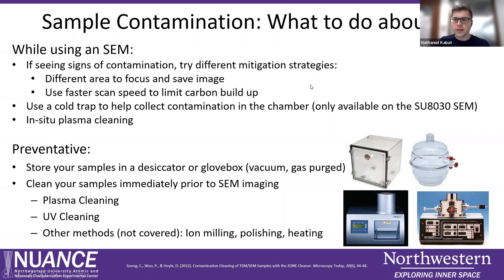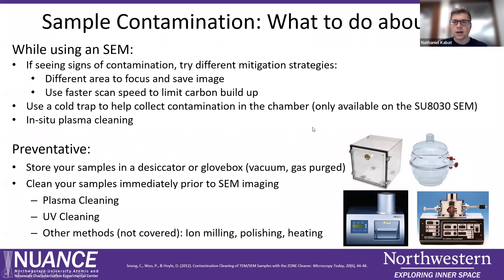Let's talk about a few different things you can do to mitigate, minimize, or attempt to fix contamination altogether. While you are actively using an SEM, you can do your focusing and alignments at a high resolution in a different area from where you save an image, to minimize buildup in the areas where you collect an image. In some cases you can simply use a faster scan speed to help limit carbon buildup, although you may not get as much signal. We have a few specific add-on tools you can use on the SEMs. You can also use a cold trap, which uses liquid nitrogen to help collect contamination in the chamber — this is available on one of our SEMs, the SU8030. Another technique is an in-situ plasma cleaning technique, where once you've loaded your sample into the microscope, you can use a plasma cleaner in that context.